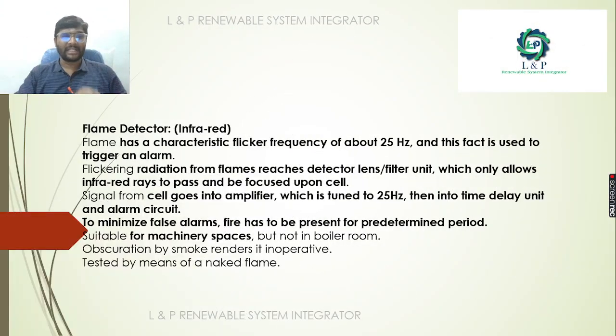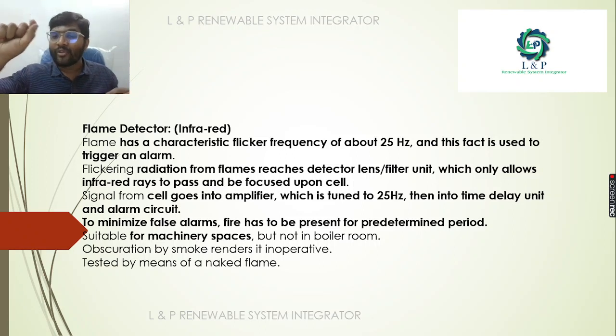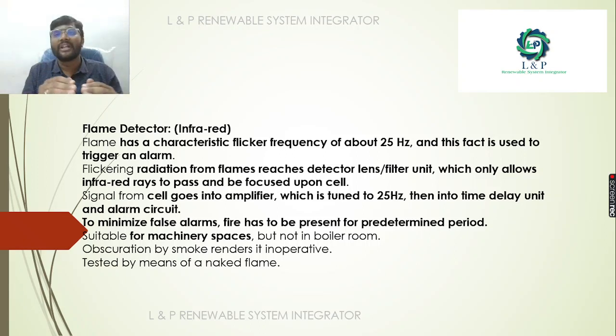Next are the flame detectors. Flames have a characteristic flicker frequency of about 25 Hz. When the flickering radiation from the flame reaches the filter unit, which allows the infrared rays to pass, it is focused upon the cell. Signals from the cell go into the amplifier, which in turn is tuned to 25 Hz, then into the time delay and the alarm circuits. To minimize false alarms, the fire has to be present for a predefined period.